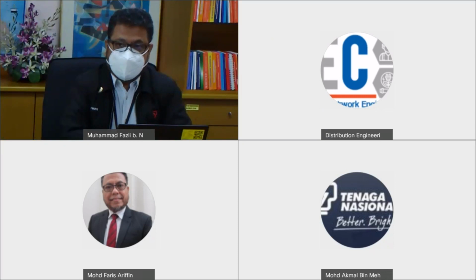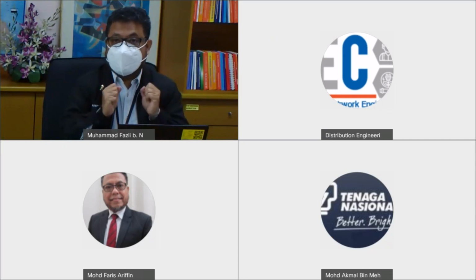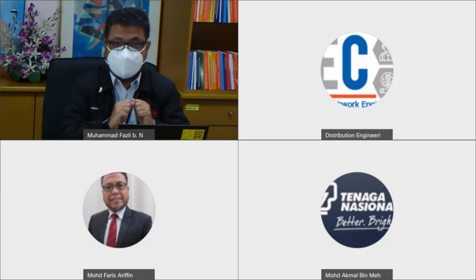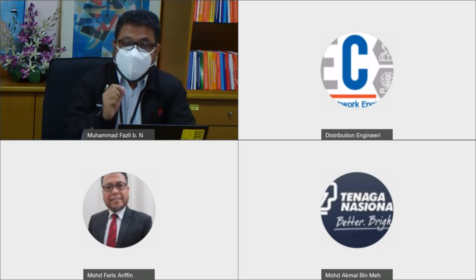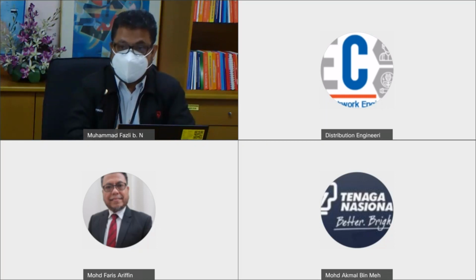Similarly, we can put the arcing horn and ensure that the gap is 40 cm for both the glass and the porcelain insulator. However, there is an issue with porcelain insulator. For example, if the impulse is too high, the glass insulator will rupture and be blown to pieces. But for porcelain, mechanically, it is higher in terms of strength, but electrically it's not as good as glass insulator. And when there is damage on the porcelain insulator, you have these micro cracks, and these micro cracks cannot be seen with the naked eye.